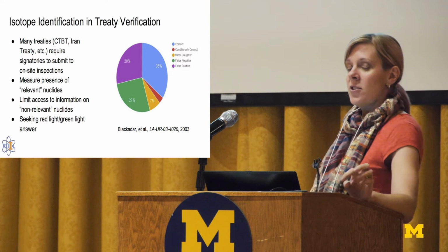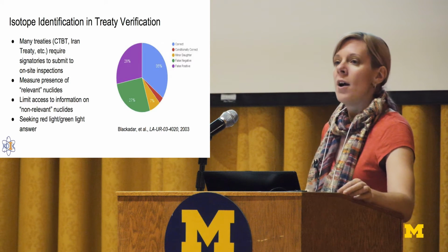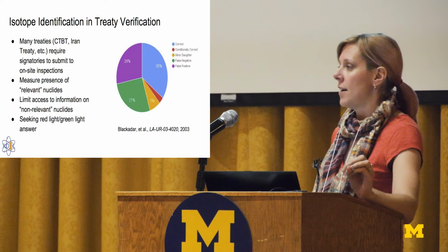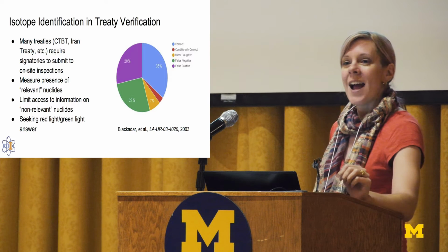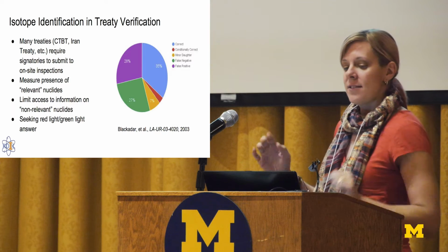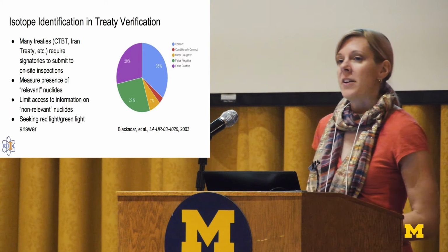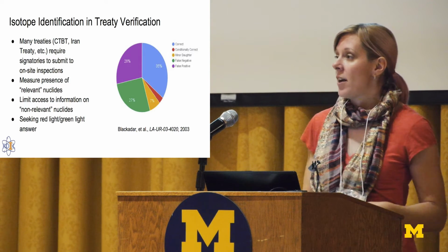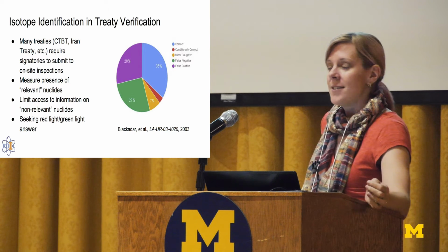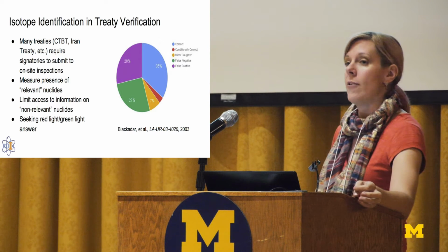Back when I was doing isotope ID evaluations at Los Alamos, and these are old results, this is 2004, what we were observing was particularly off of sodium iodide-based handheld isotope identifiers, the automated identification accuracy was very poor. And what we were seeing was that these identifiers would maybe get the right answer maybe 35% of the time. They were all based off of sodium iodide. Some of the detectors used in the evaluations are the very ones that the IAEA goes out and does inspections with. So the question is, can we somehow improve the automated isotope identification capabilities of these handheld radioisotope identifiers?